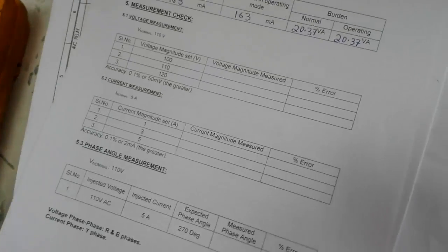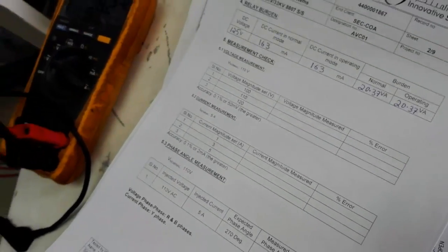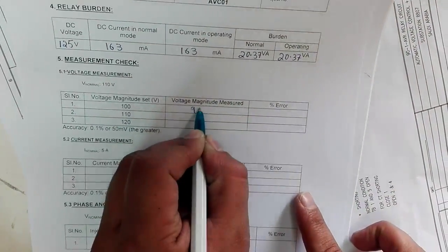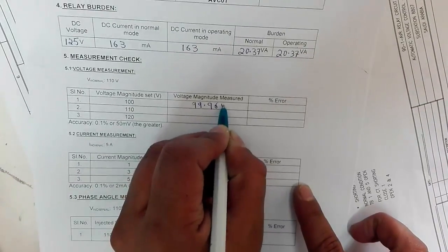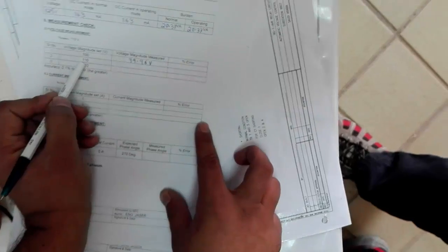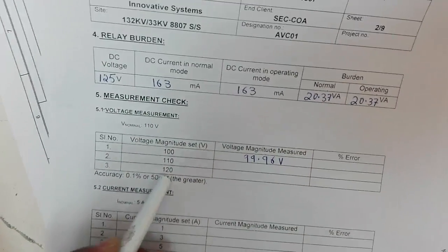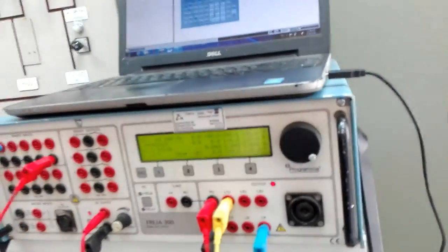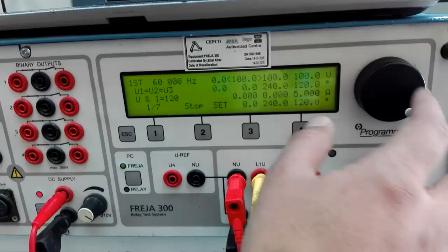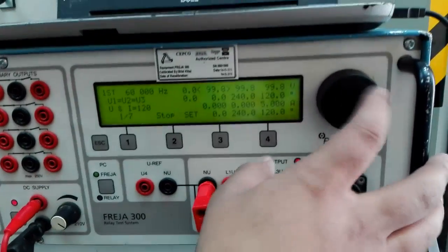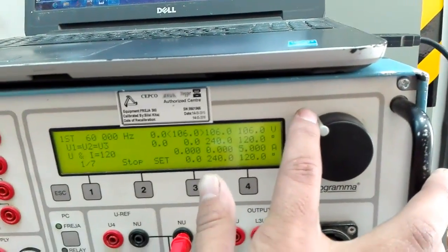After this 99.96 we have to write the value. For applying 100 volt AC and taking the reading from our ZIV relay, it comes 99.96 volts. Now similarly, we will apply 110 volts and 120 volts, and then we will write those values. No problem if we use the multimeter and if we use the Frisia, but better we use Freja directly, to minimize error. Now simply apply 110 volts.